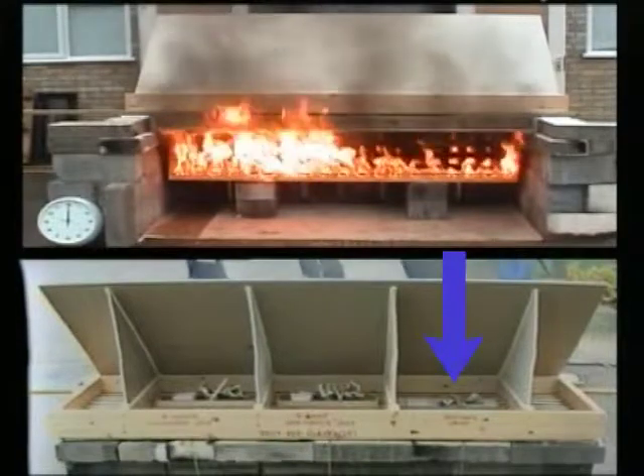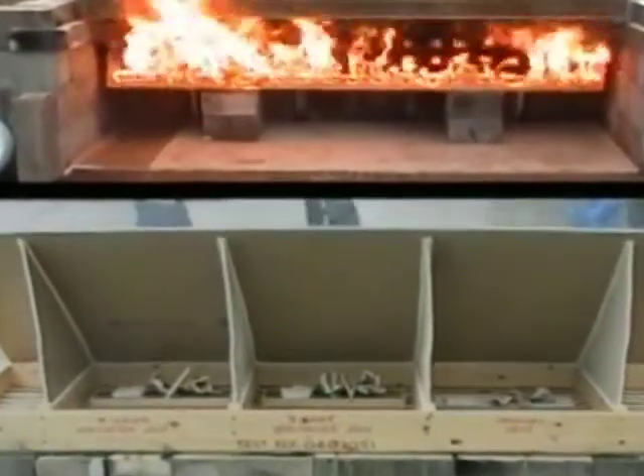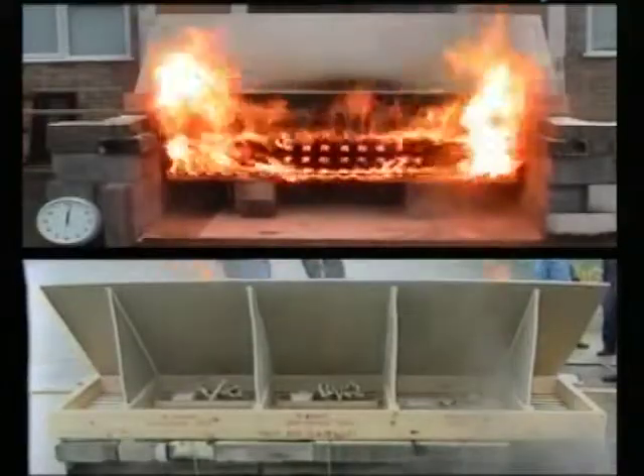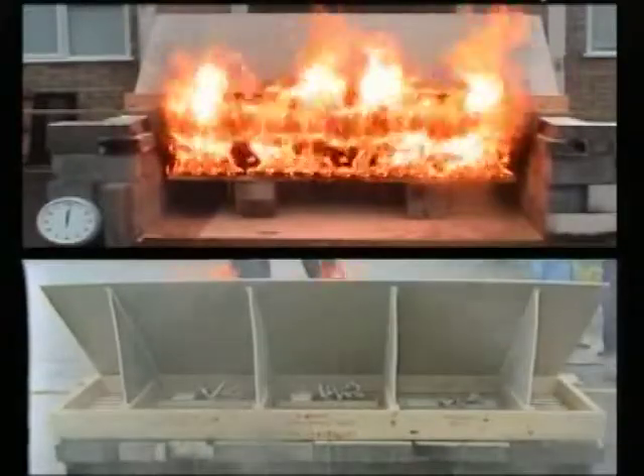The third is a conventional intumescent damper. On top of all three vents, at the protected side inside the attic, are positioned realistic materials that easily ignite: crumpled paper, cotton waste, and wood shavings. To simulate typical breaking of a window pane and consequent fire flashover, a steel baffle keeps the vents protected during the burn-in period, in which the crib fire grows to exceed five megawatts of power.